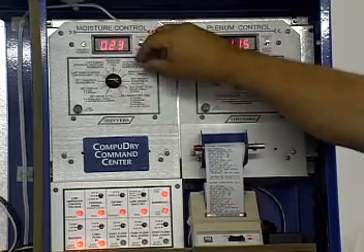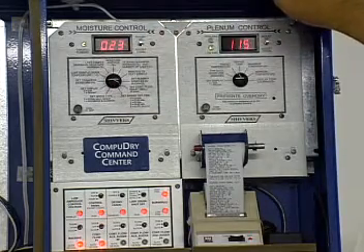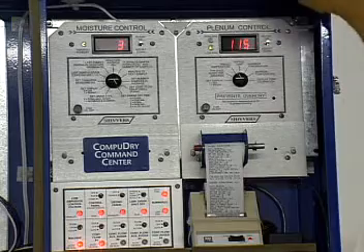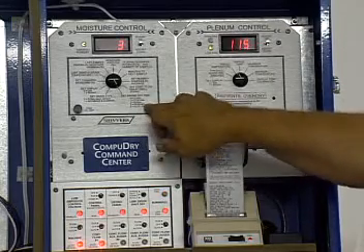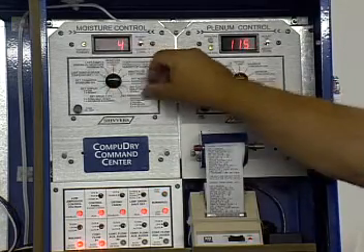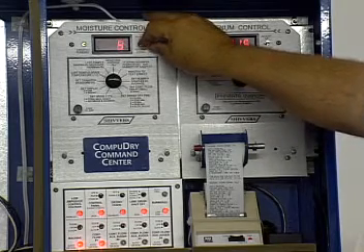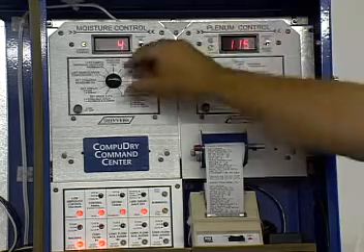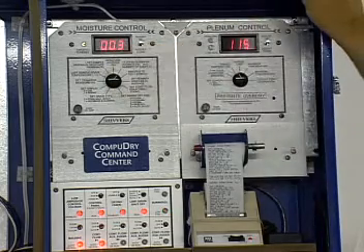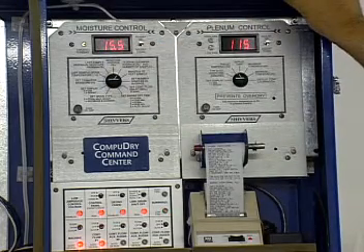We have the continuous flow setting. We've set that before for 23 seconds. We have the sweep at number 3, which is the 20 to 60. We have the average here at 4 for circulator 2, 7 for circulator 1. This is circulator 2, so let's go back to 4, and we have everything set. Made 3 transfers. The average is 15.5.